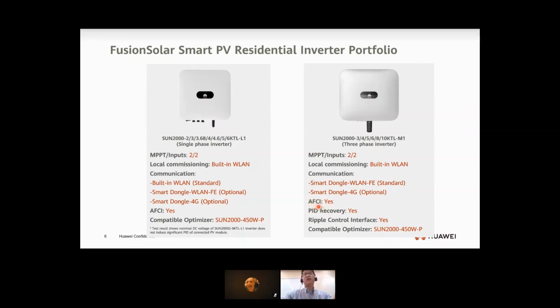AFCI is also a standard feature in our residential inverters on the 3-phase one, and because the 3-phase inverter has an even higher DC voltage, with almost 800 to 1000 V operating voltage, the PID becomes a problem. PID is potential induced degradation, which is a module problem that will affect the output performance. Say the new module's output is 360 watt or 400 watt, because of the PID problem the output power will be reduced to 90%. The main reason causing PID is the high voltage difference, like this one, a 1000 V DC system. Another reason is the humidity and the high temperature. All these 3 factors will cause PID effects.